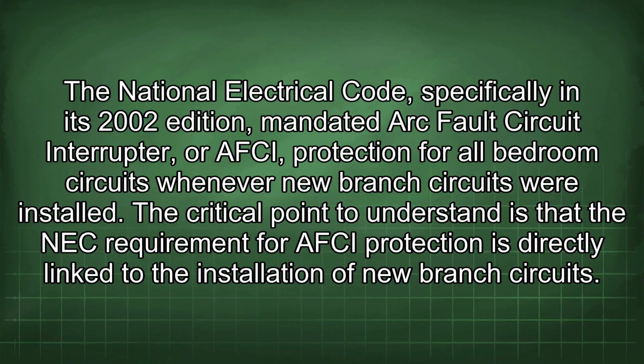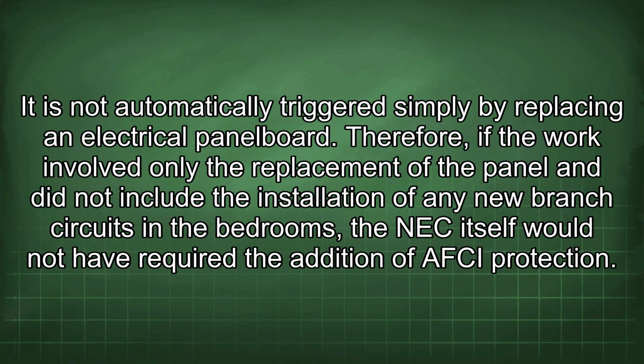The National Electrical Code, specifically in its 2002 edition, mandated arc fault circuit interrupter, or AFCI, protection for all bedroom circuits whenever new branch circuits were installed. The critical point to understand is that the NEC requirement for AFCI protection is directly linked to the installation of new branch circuits. It is not automatically triggered simply by replacing an electrical panel board. Therefore, if the work involved only the replacement of the panel and did not include the installation of any new branch circuits in the bedrooms, the NEC itself would not have required the addition of AFCI protection.